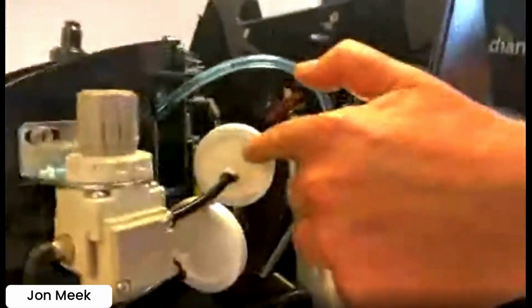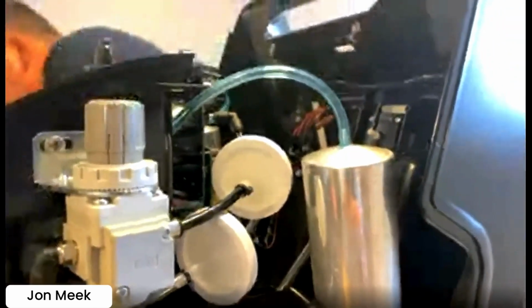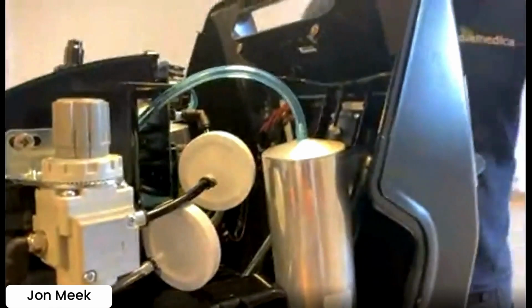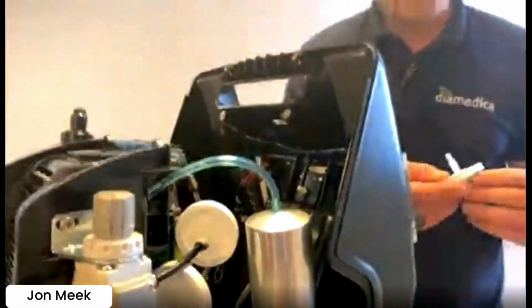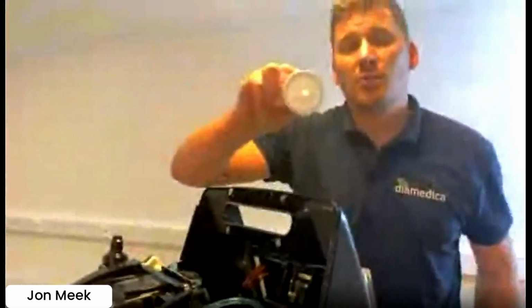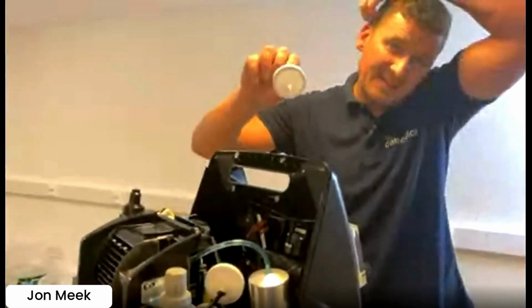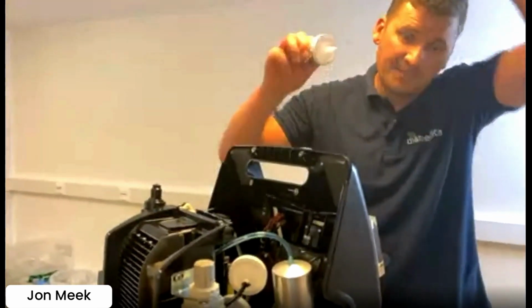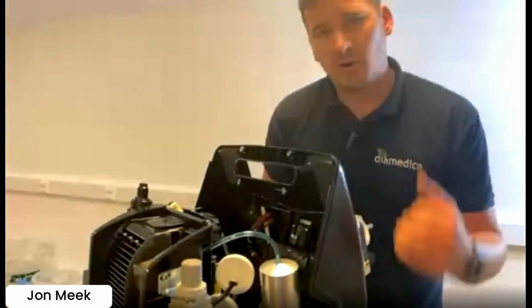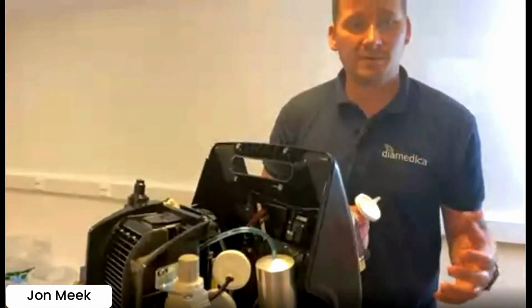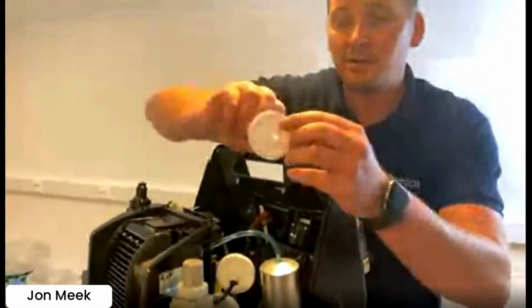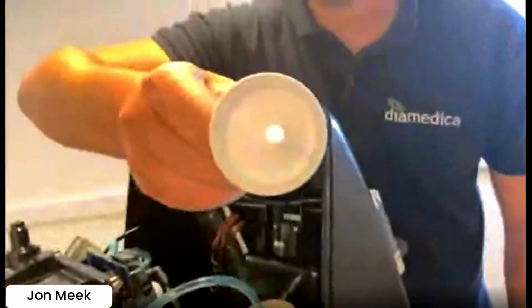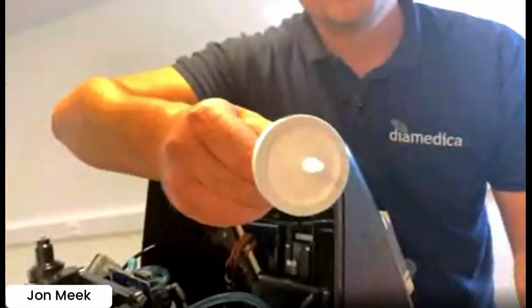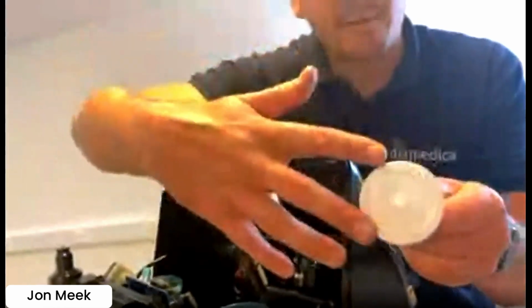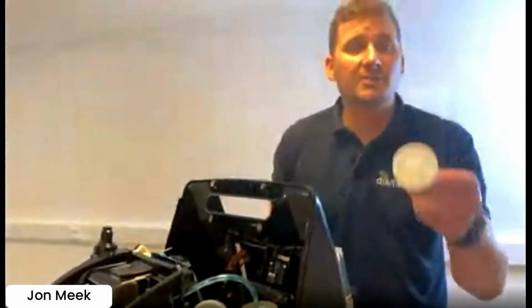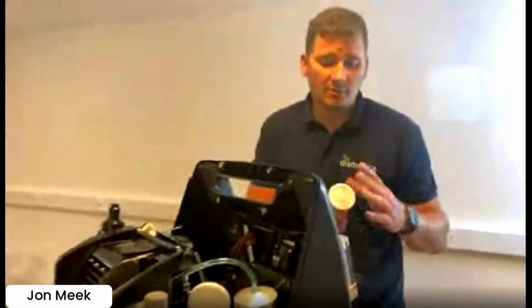it then goes through your HEPA filter. So these are your fine bacteria filters, removing any fine particles, anything that's supplied for the patient. Really important. These will probably need to be replaced every 18 months, maybe 24 months. They will last longer if the environment is a lot cleaner or you maintain your filters a lot more. They are only one directional. So there is an "in" written on it. If you put them the opposite way, they will become a barrier and then they will not work. So you need to ensure the direction of flow is correct.